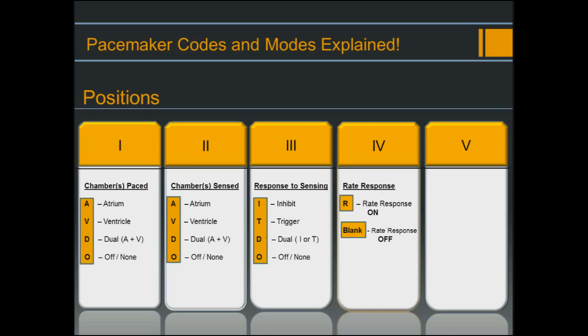The fourth position represents rate response or rate adaptive pacing. This position is represented by the letter R if rate response is on, and is typically left blank if rate response is turned off. The fifth position represents multi-site pacing, but it really isn't used, so we won't be discussing it further in this presentation.